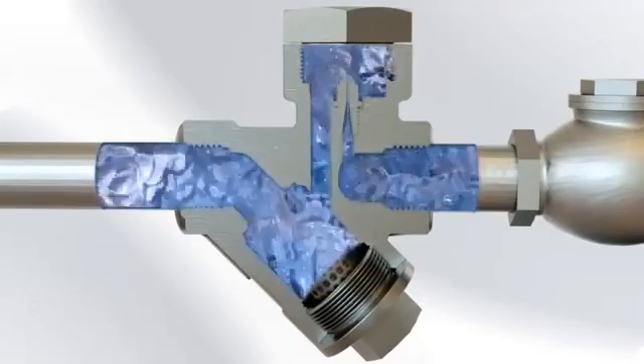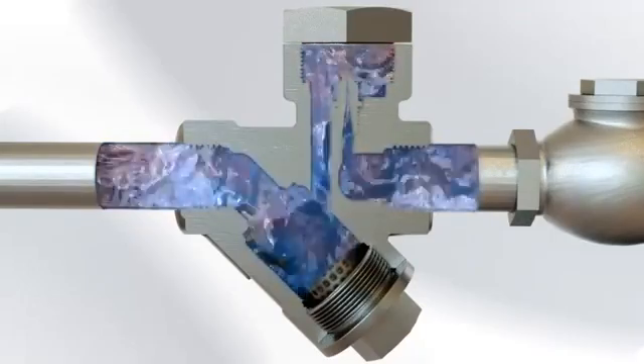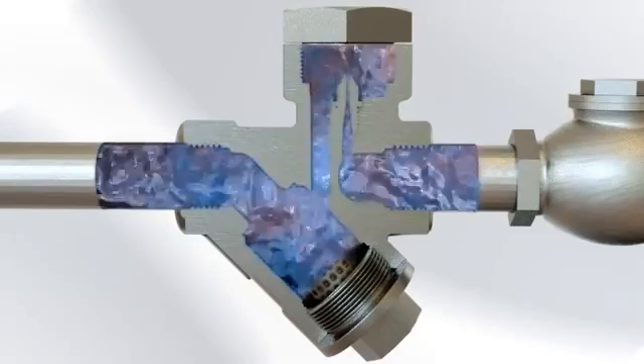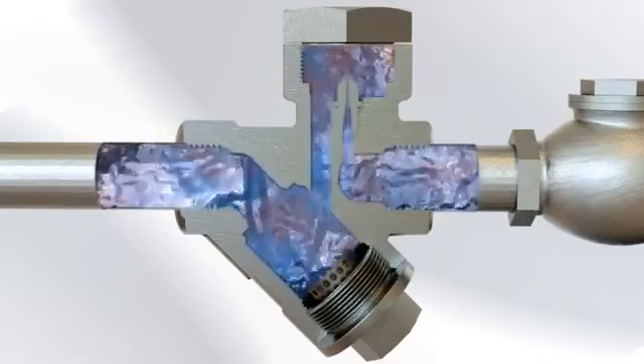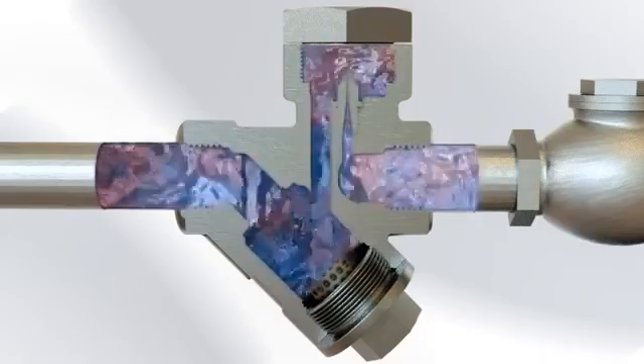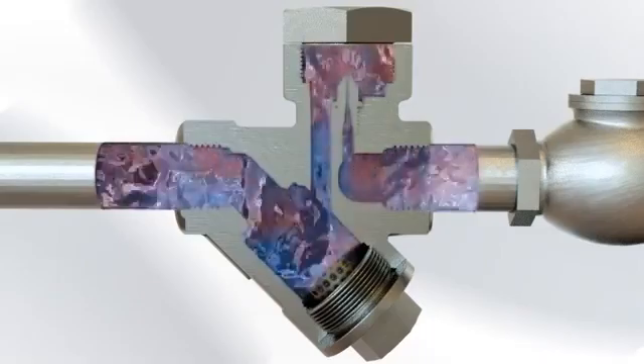Once all the cold condensate and non-condensable gases have been ejected, steam and hot condensate reach the Delta Steam Trap. As the steam continuously condenses to hot condensate in the pressurized steam system, it is fed to the steam trap by the pressure in the system.